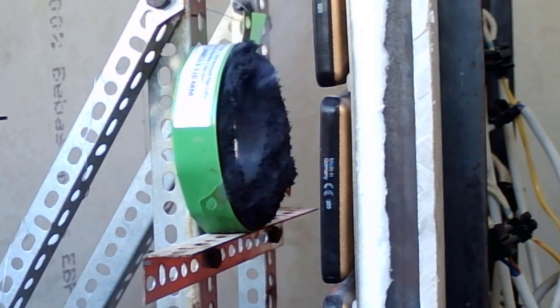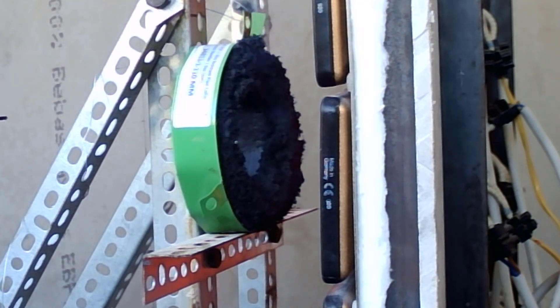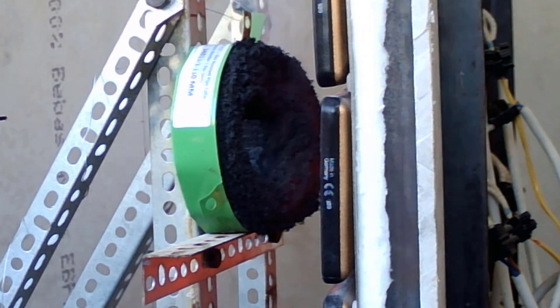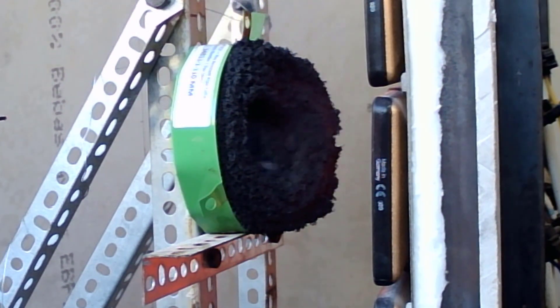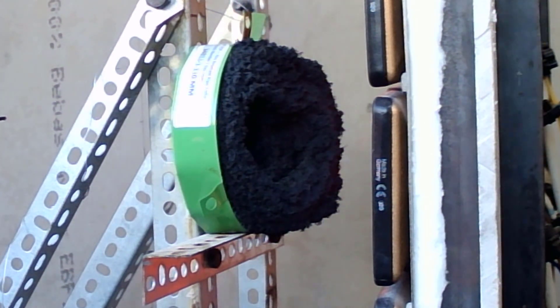Here the pipe collar is being tested and you'll see it swell up and gradually close off the hole in the middle. The way we're testing it isn't 100% representative — you need a lot more heat for it to fully close — but at least you can see how this intumescent grows and would eventually prevent fire from coming through the opening once the pipe has melted away.